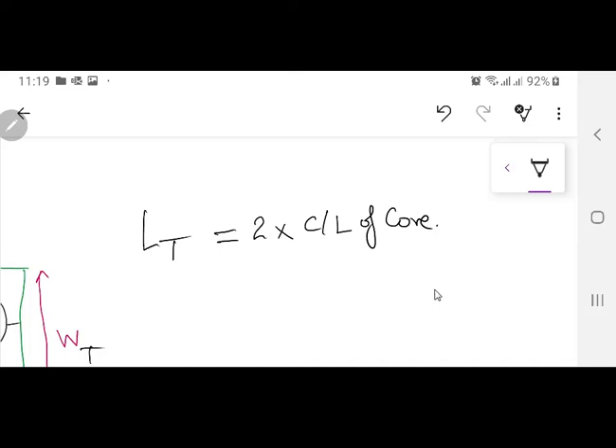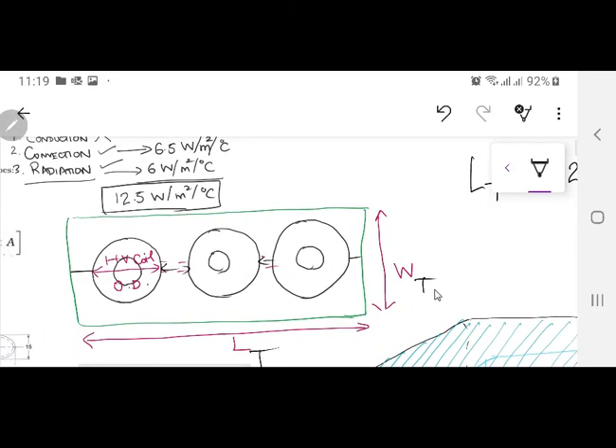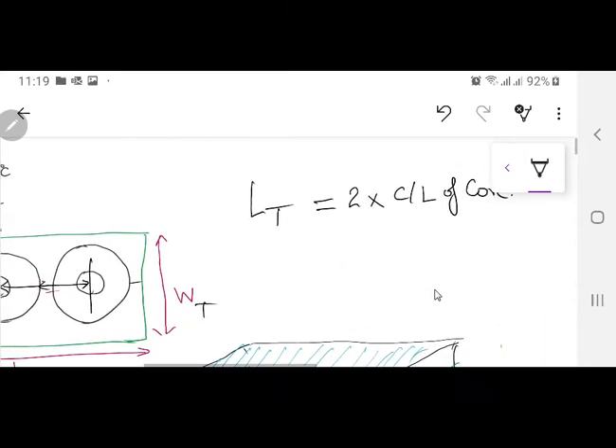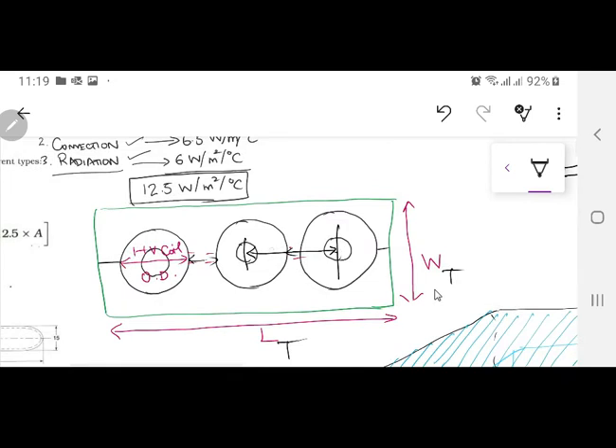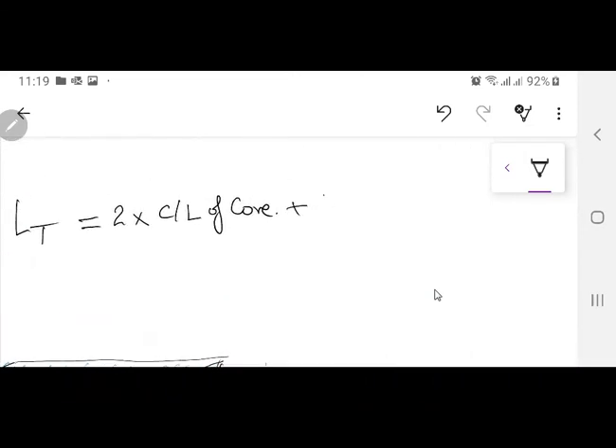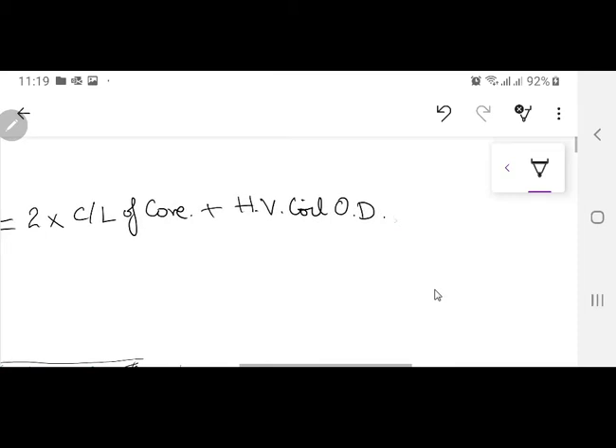What was CL? Do you remember? Core limb, from the center of one to the center of the other one. So what is this distance? This is from this point to this point. So when I have 2 into CL of the core, meaning from this point to this point added up, then plus the high voltage coil outer diameter, and then the next thing is the clearance distance added.